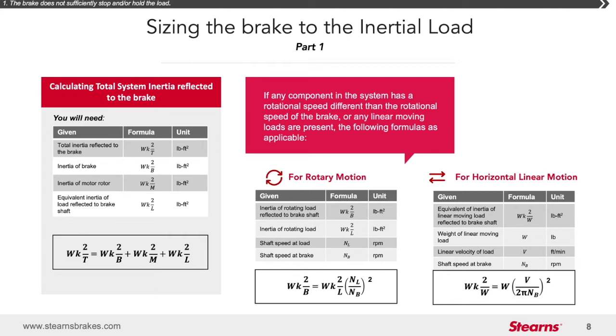The second formula deals with rotary conditions. Rotary could mean a rotating table, saw blade, or any application where the actual load movement is rotational. To calculate rotary motion, total system inertia reflected to the brake shaft is equal to total inertia of the rotating load times the shaft speed of the load divided by the shaft speed at the brake squared.